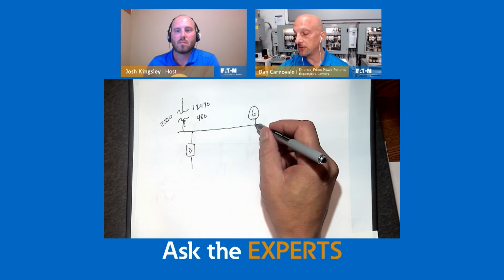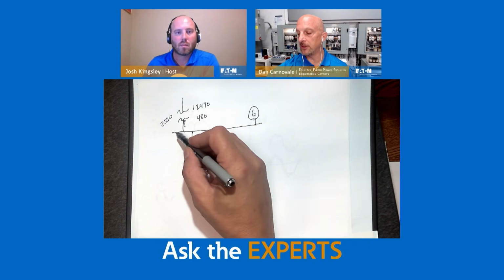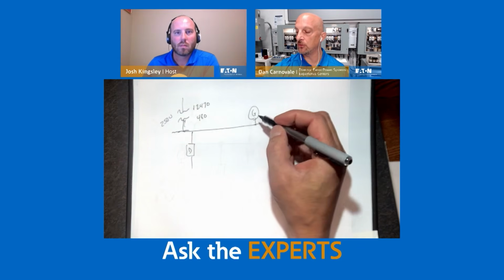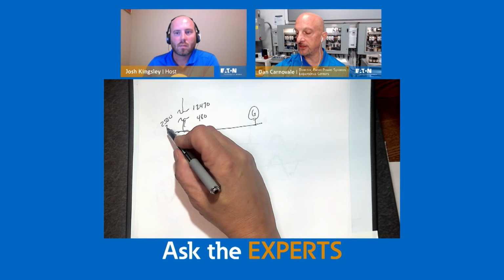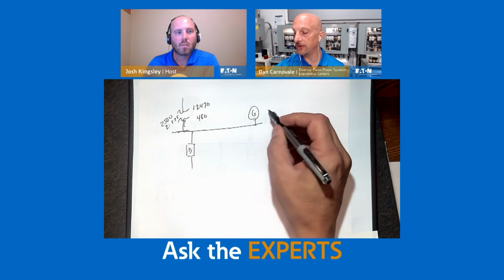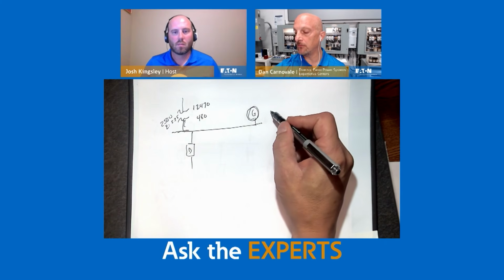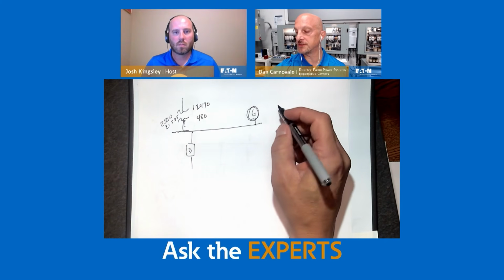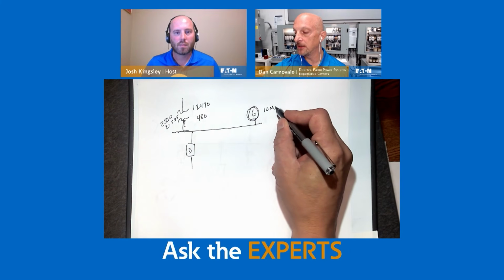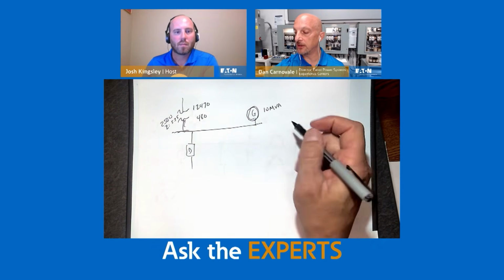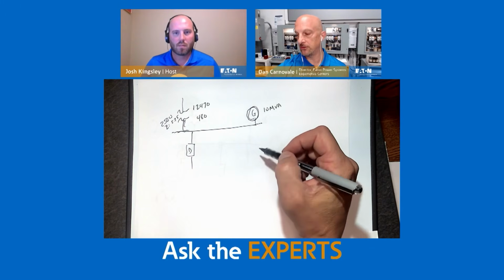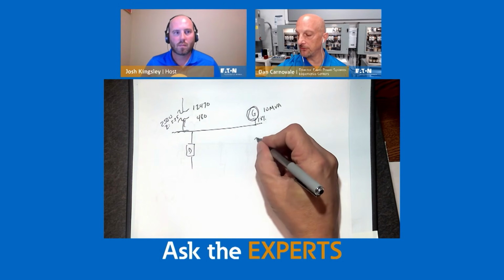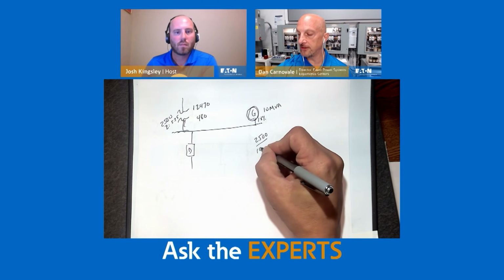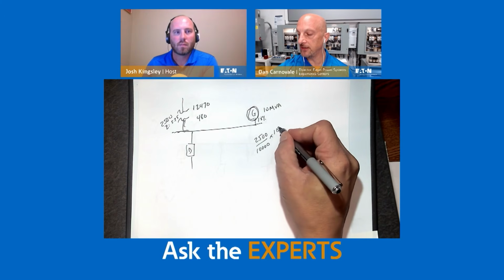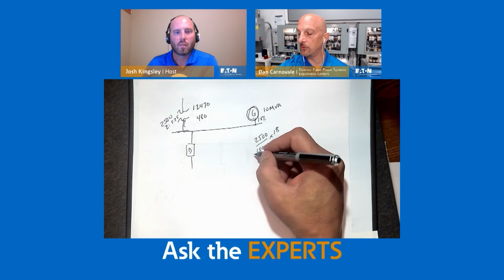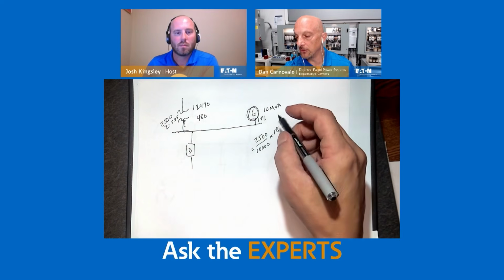Now, as far as voltage goes, what he may be saying is it runs a lot better on the generator. The opposite could be true in terms of impedance. Remember, we said this Z is 5.75. If for some reason he had a very large generator here, it's a comparable thing. So if this was, let's just exaggerate it, say 10 MVA, 10 MVA would be 4 times bigger than that. So even though the impedance is bigger in terms of 18%, the effective impedance would be 2,500 divided by 10,000 times 18. So you end up with something that's going to be closer, or actually less than the original impedance.